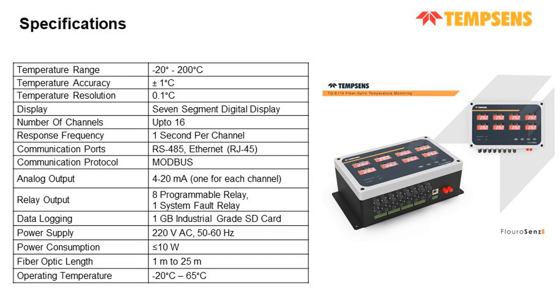The communication ports for digital communication are RS485 and Ethernet, which work over the Modbus protocol. And there is an analog output of 4-20 milliampere, the industrial standard, one for each channel. There are 8 relay outputs so that you can control up to 8 alarms or 8 different systems. Then there is a data logging capability, with a 1 GB industrial SD card provided, and it runs on a power supply of 220 volt AC, 50-60 Hz frequency, and consumes less than 10 watts. The maximum fiber optic length that the controller supports ranges from 1 meter to 25 meters, and the operating temperature of the controller is -20 degrees centigrade to 65 degrees centigrade.